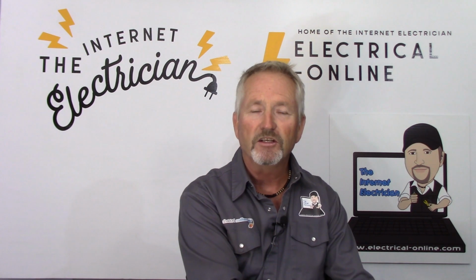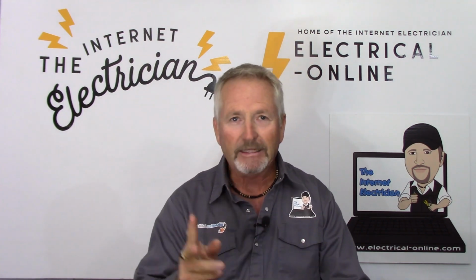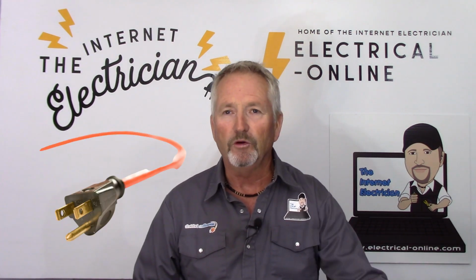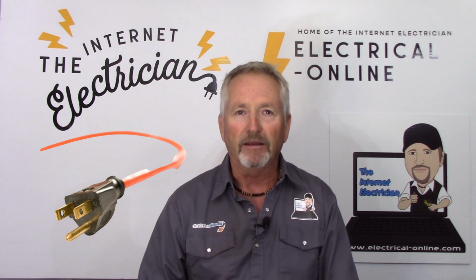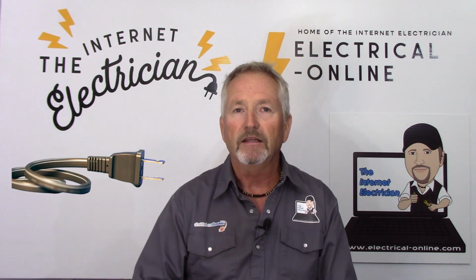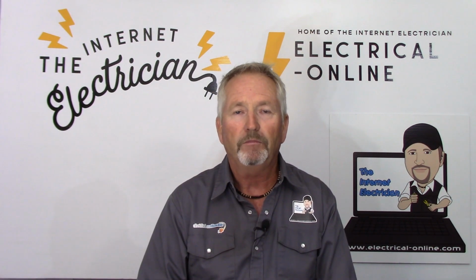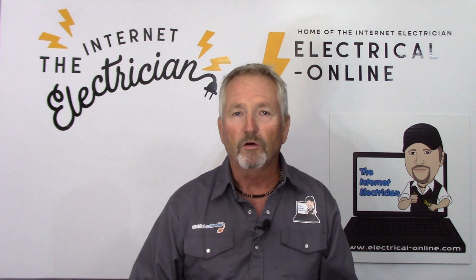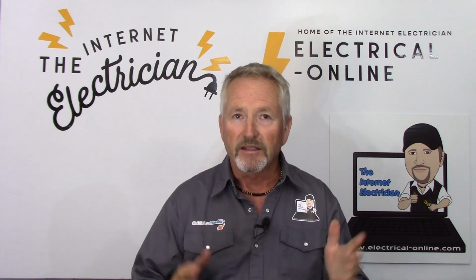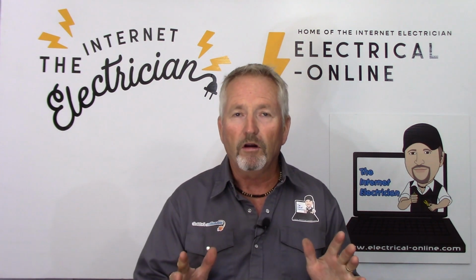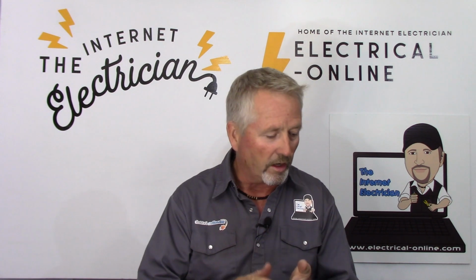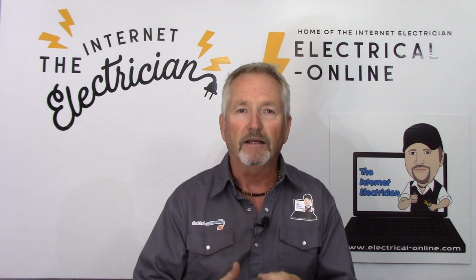If you've got an extension cord that it broke off, cut that cord and put on a new aftermarket end on it, because it's not good. Now, there are two prong devices. There's double insulated hand tools that don't need a ground prong, and to use an extension cord that is only a two prong at both end is fine for that, because it's double insulated. Should something go wrong inside the tool, there's no way you can contact the hot wire from inside that tool and get a shock.